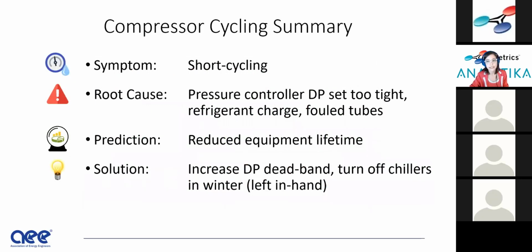So the symptom here was short cycling. The root cause was the pressure controller DP was set too tight. Other causes can be refrigerant charge and things like that. The prediction was a reduced equipment lifetime. We didn't take savings here, but you absolutely can take avoided costs for replacing that potential piece of equipment. And here the solution is to increase that DP deadband to give it a little bit of room, but really the chillers were not supposed to be on. They were left in hand in this situation. This was serving a vivarium, I think.